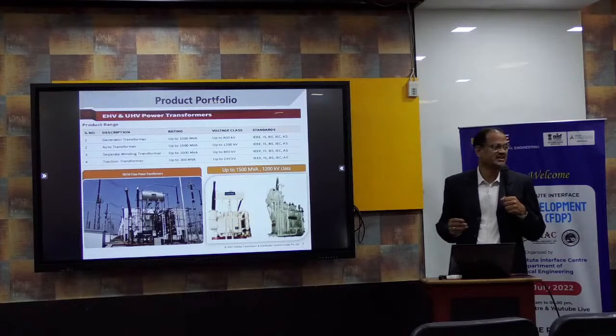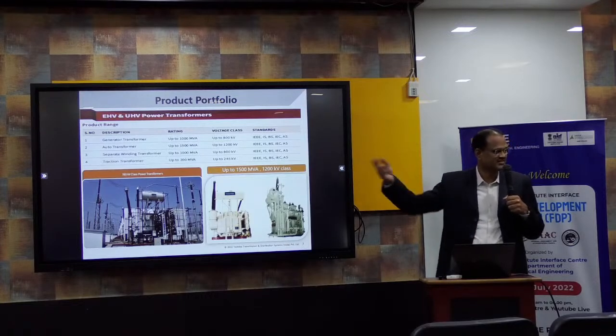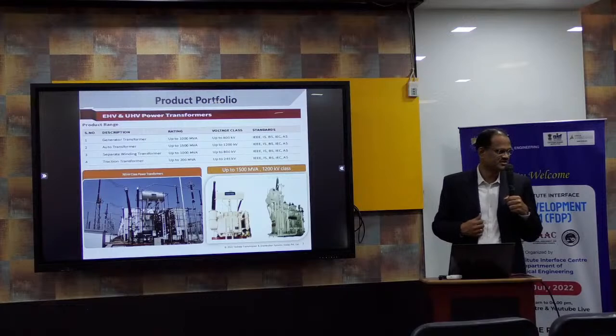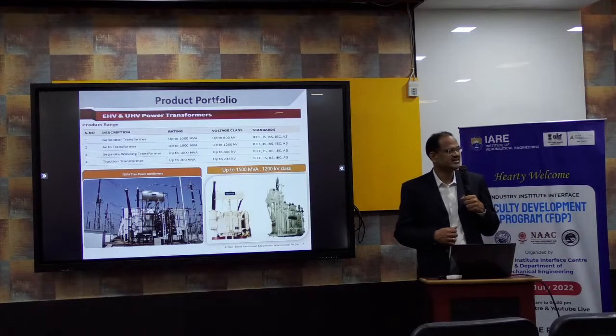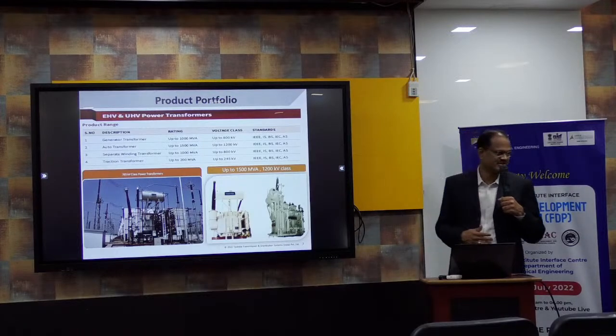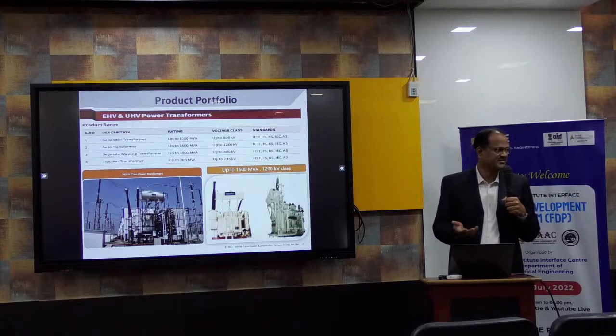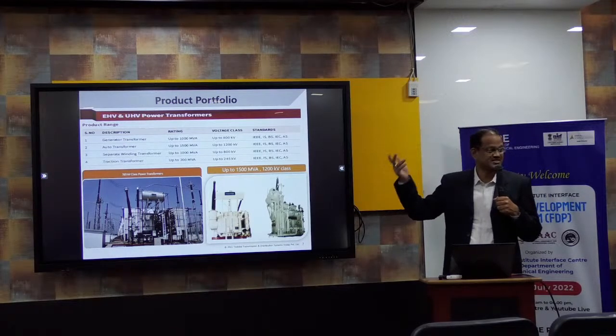A small house requires a 100 kVA transformer. One apartment requires a 160 kVA transformer. A college requires 1000 kVA or 500 kVA. Power transformers in generation are in MVA. 1000 kVA is equal to 1 MVA. So 500 MVA, 315 MVA, large transformers like that will be there in the substations and generator stations.